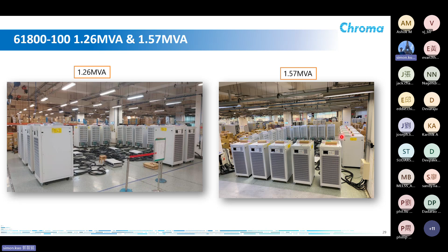I mentioned about the testing wire distance that will affect the inductance, which will cause trouble to the customer during testing. If you go into higher current, the effect becomes higher. Therefore, by doing this kind of system integration, we can replace the wire connection with a bus bar. Chroma has our own patented low inductance bus bar design for our loads.